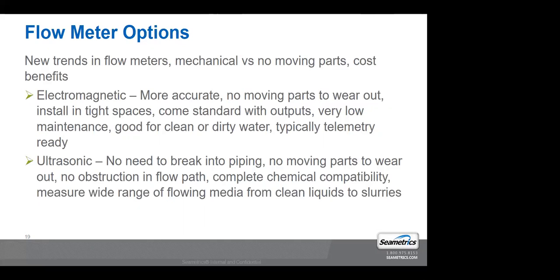The other thing is with magnetic flow meters, they typically come with a lot of features on them that you may use today, you may not use today, you might use them later. But they come with things like a pulse output. A lot of them come with a data logger built into them, bidirectional flow reading. So you'll have forward flow, it's constantly accumulating forward flow. If flow runs in reverse, it'll capture that information as well. They have pulse output in it. If you need it, great. If you don't, it's there if you want to hook it up years later.